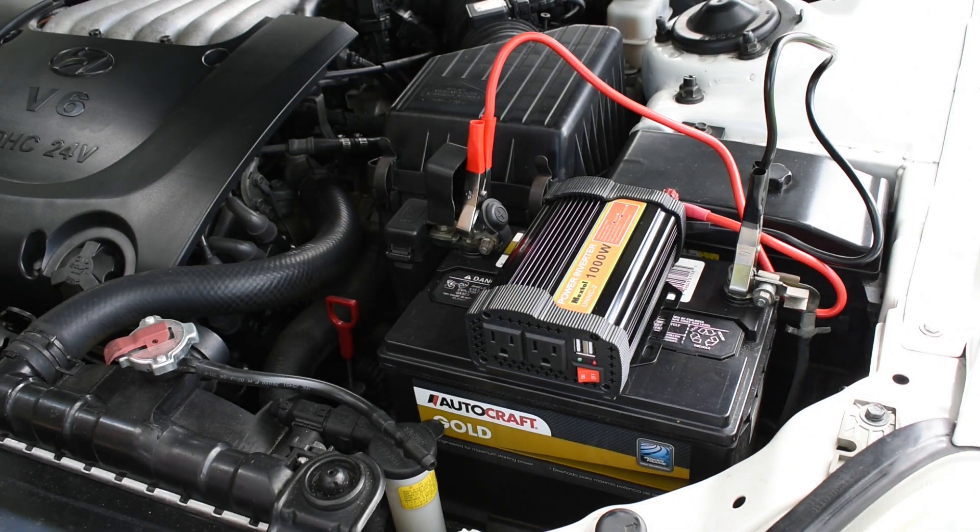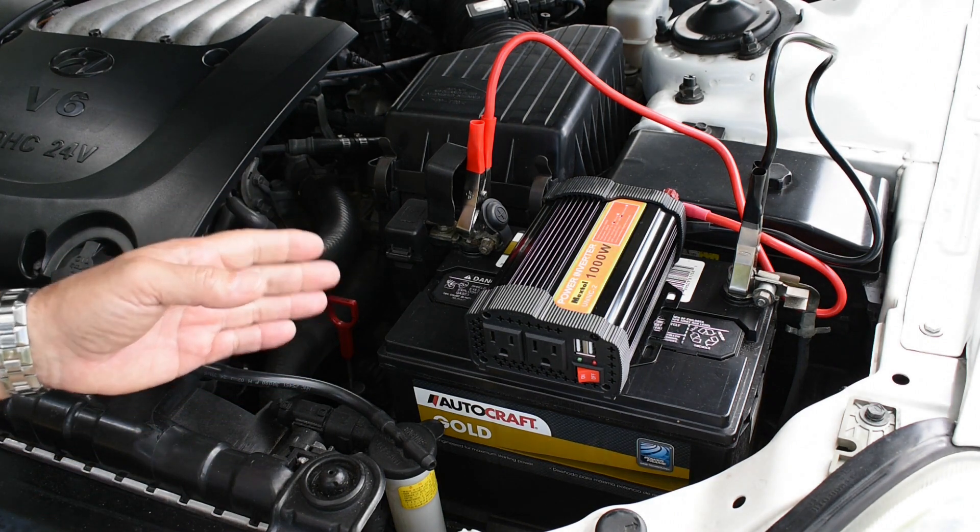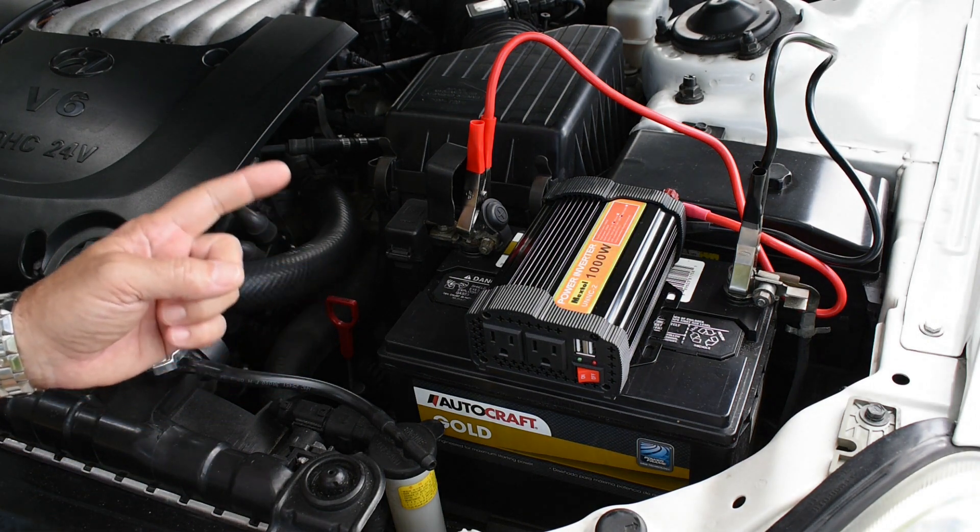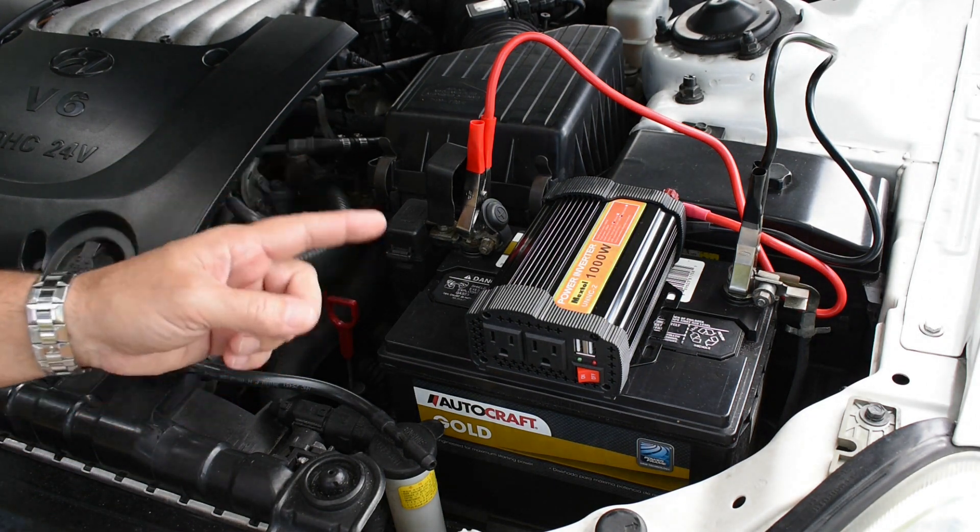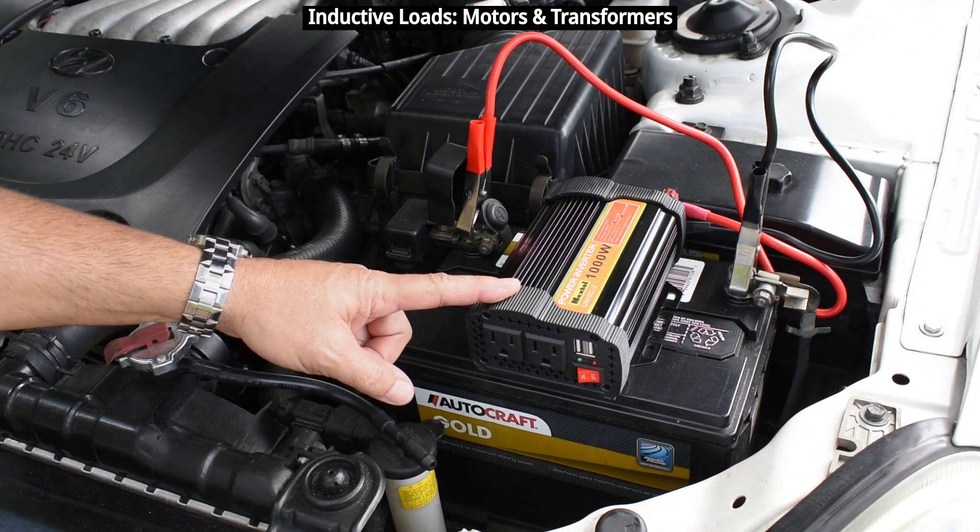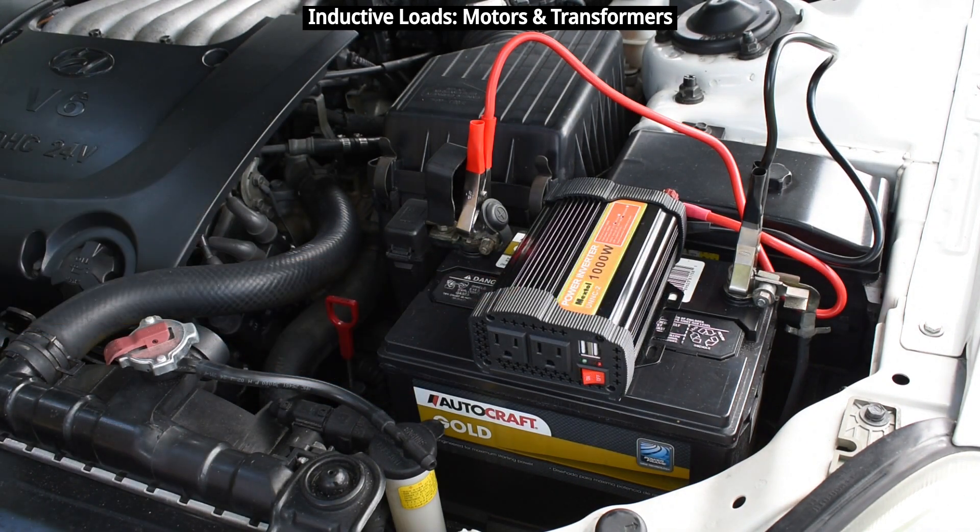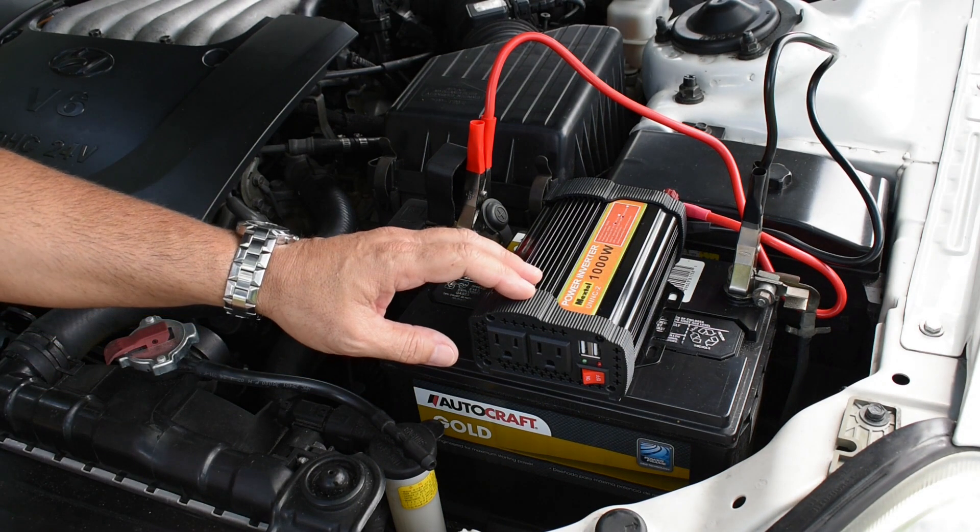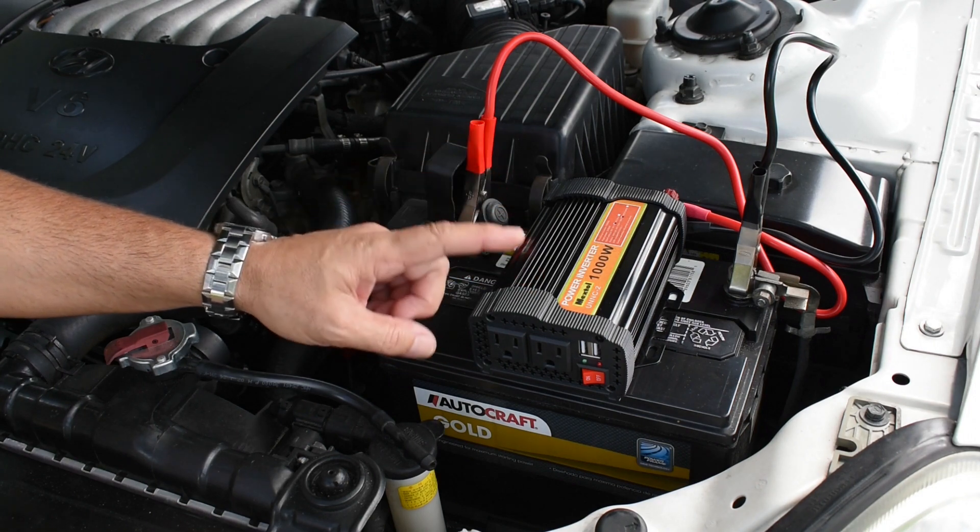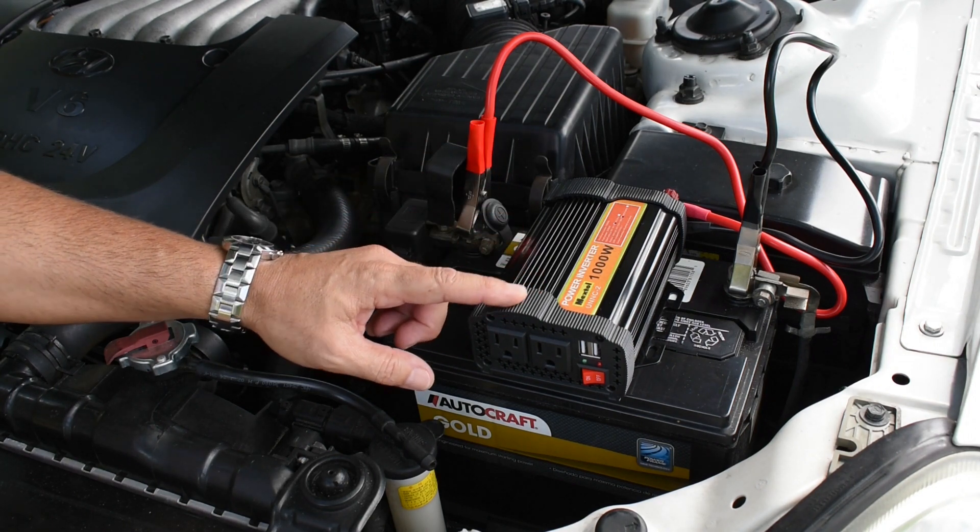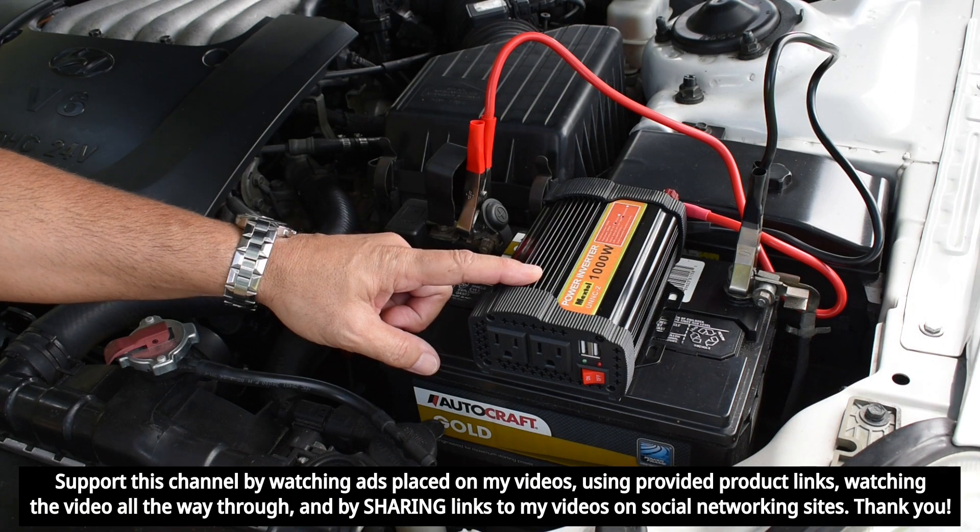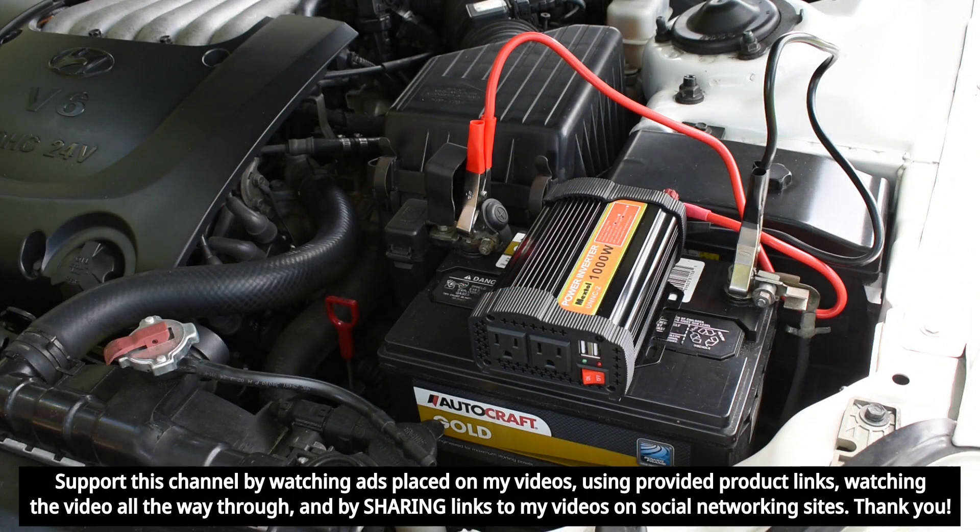When using resistive loads, the problem is non-existent, but when you use an inductive load, that's when you're going to observe the problem. So in this video, I'm going to show you an extremely useful tip that's going to help you get those higher inrush current inductive loads to start right up with your generator or power inverter.